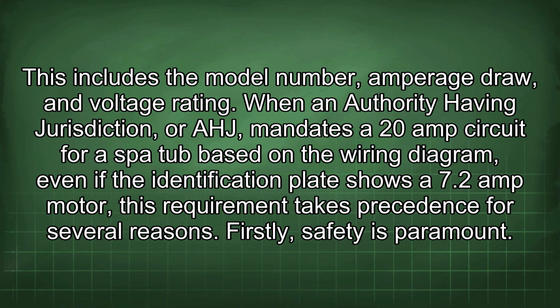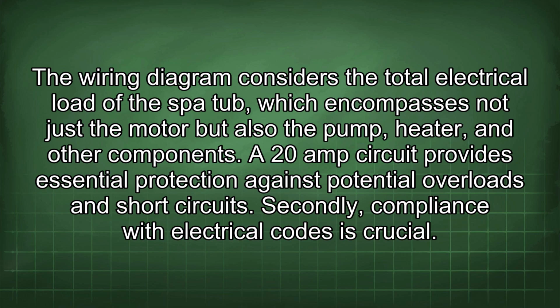When an authority having jurisdiction, or AHJ, mandates a 20 amp circuit for a spa tub based on the wiring diagram, even if the identification plate shows a 7.2 amp motor, this requirement takes precedence for several reasons. Firstly, safety is paramount. The wiring diagram considers the total electrical load of the spa tub, which encompasses not just the motor but also the pump, heater, and other components. A 20 amp circuit provides essential protection against potential overloads and short circuits.